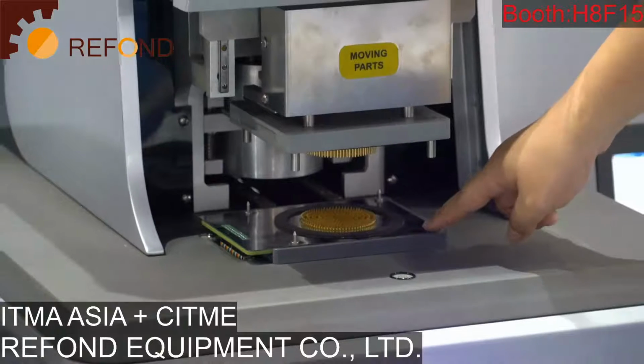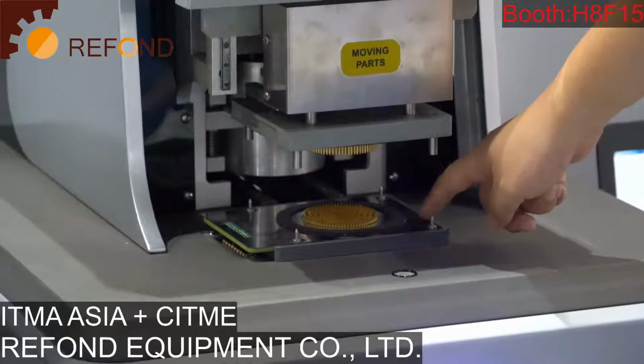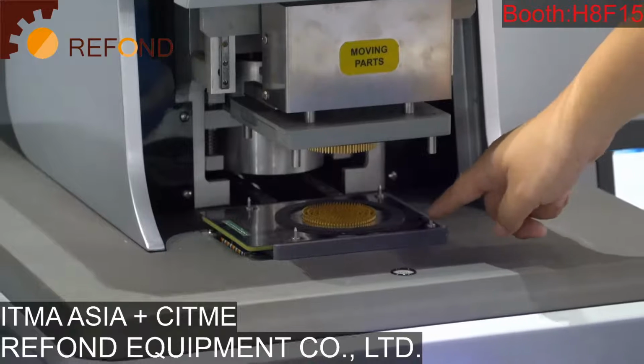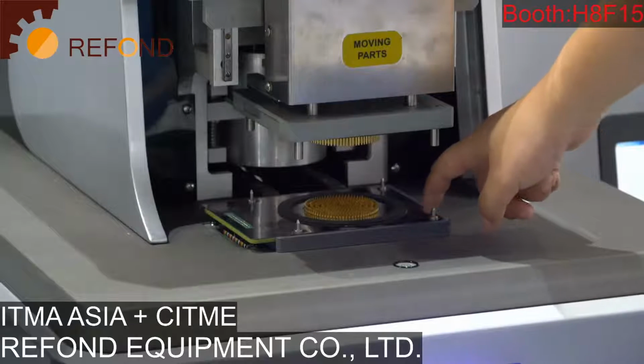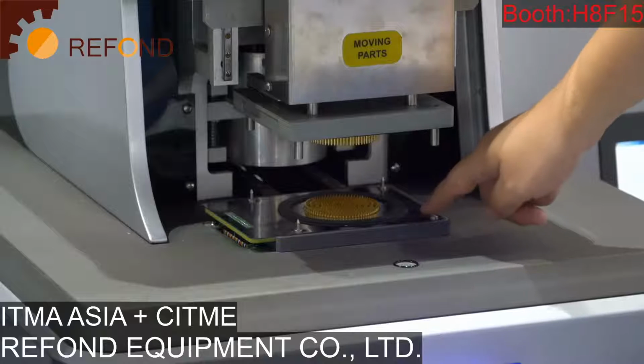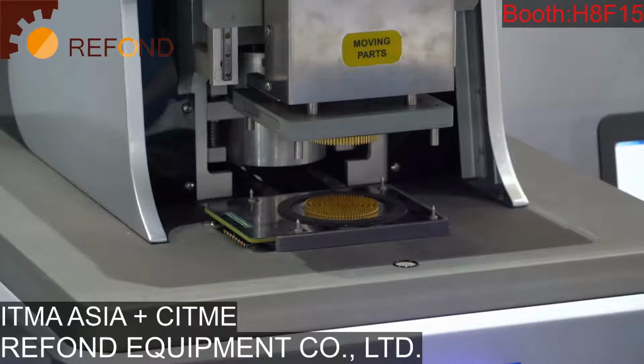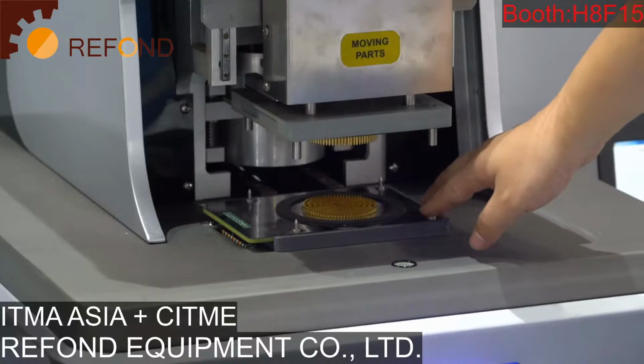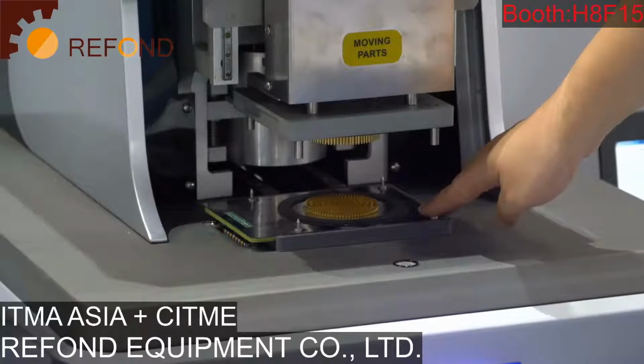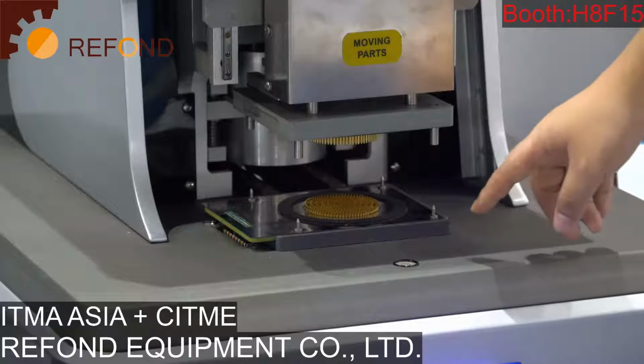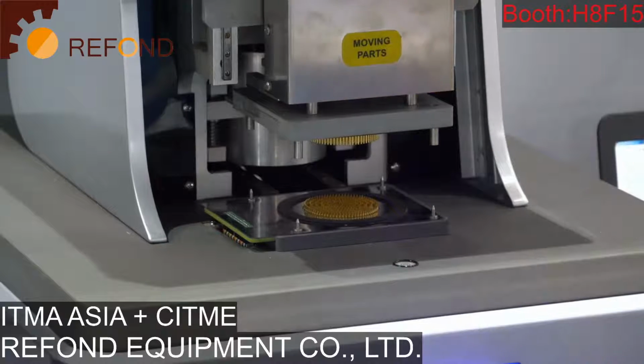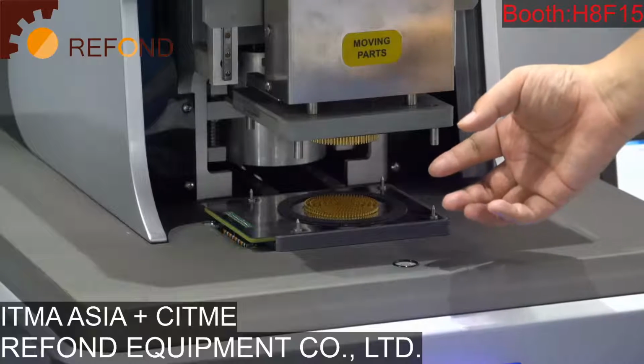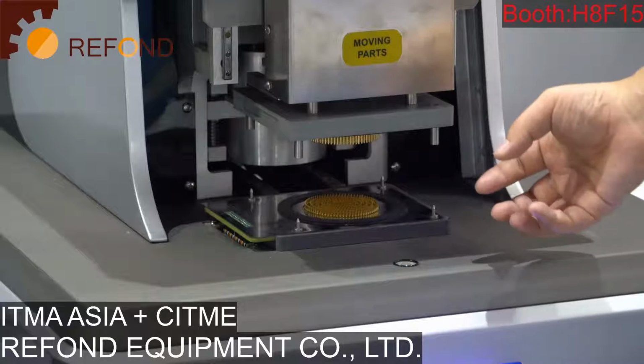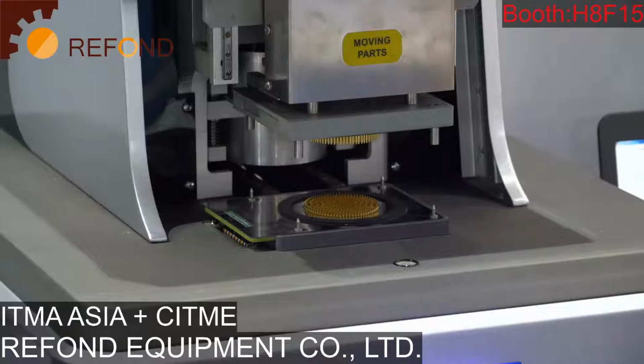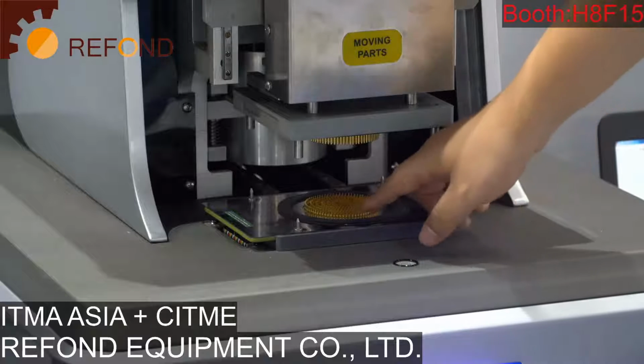In addition to the requirement of the standard, we made a lot of innovation. First of all, the amount of water to be pumped required by the standard is 0.2 milliliters, and we made it adjustable to a range of up to 0.45 milliliter, with still the same precision required by the standard. So you can choose to use a different amount of test liquid for the test, other than the one required in the standard.